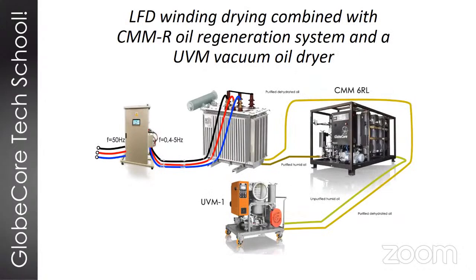Okay, here we've got a winning combination of an LFD, a CMMR regeneration system, and a UVM vacuum oil dryer. Of course, here we also heat the windings, then water goes from the insulation into the oil, and then we pass that oil through the thermovacuum system like the UVM, removing water from the oil and filtering it. However, the regeneration plant that you can see here, the CMM6RL in this case, improves the chemical composition of the oil. It clarifies the oil and restores it, basically. It reduces the acid number, removes all the products of oil degradation, and it pretty much restores the oil to as good as new condition. Okay, so I believe next we have our connection from Timofey, the engineer.